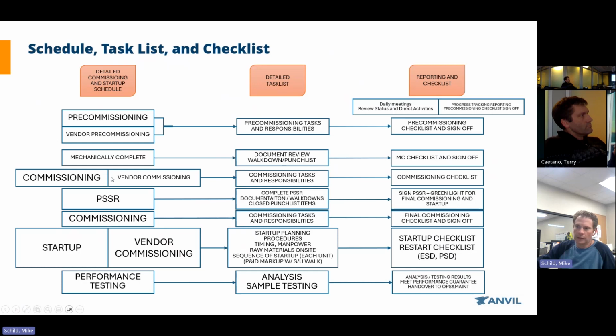Then you can see here, just to highlight, you have your commissioning. So we have the activities we can commission before our PSSR. A lot of the time you're not going to be able to commission all this equipment until it's post PSSR. So maybe I need to introduce fuel gas to light a flare. That's an example. Vendor commissioning, a lot of this stuff you have to wait for startup. Again, I have to introduce gas to the compressors at operating pressures to get my final commissioning. For pumps, I need to be making liquids or have a liquid product available to do that vendor commissioning. So that's why you see the commissioning is typically broken out in two different locations. And then finally here, the performance testing.